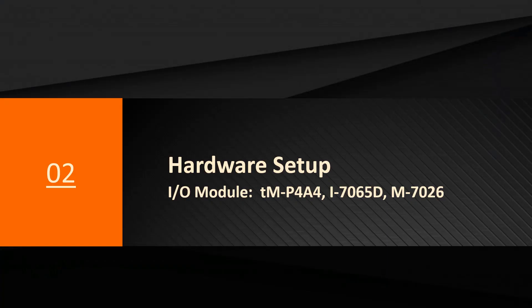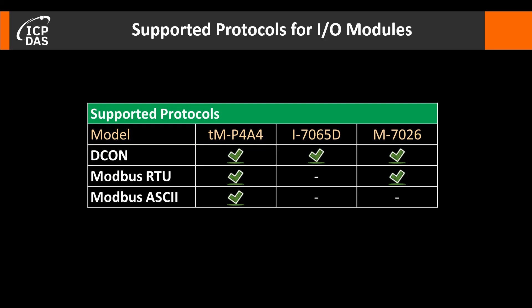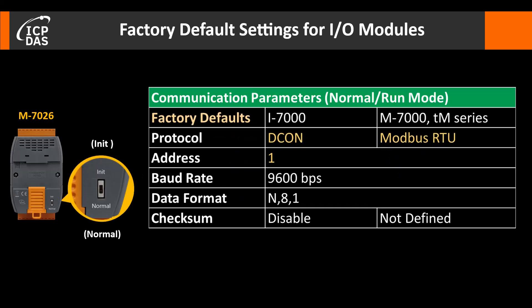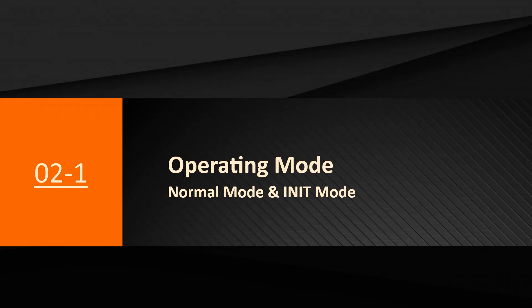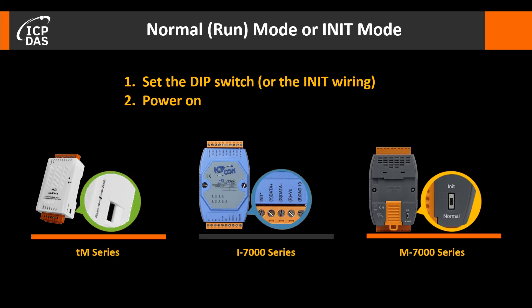In this case we use TMP4A4, I7065D, and M7026 IO modules. The TM series supports DCON, Modbus RTU, and Modbus ASCII. The I7000 series supports DCON only. The M7000 series supports DCON and Modbus RTU. The factory defaults in normal mode apply for I7000, M7000, and TM series modules. However, if the protocol setting is DCON, these four settings can only be changed in init mode.